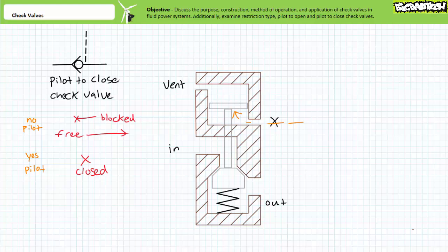the connecting rod pulls the poppet closed and fluid can no longer pass in either direction. When pilot pressure disappears, the poppet is free to move and normal check valve behavior resumes.